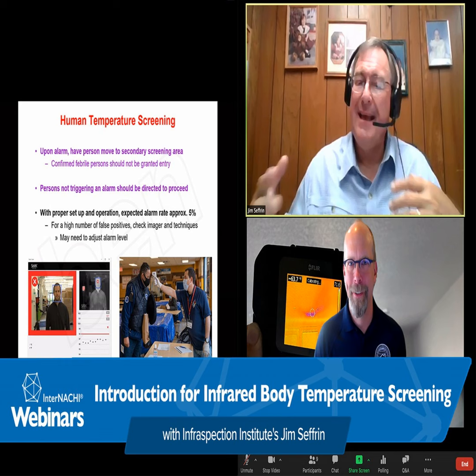I want to talk just a little bit about the need for secondary verification. Infrared is not a standalone tool when it comes to elevated body temperature screening. As part of a human body temperature screening system, we're going to have not only our imaging radiometer, or if you prefer, our infrared camera, but we also must have a clinical grade thermometer as part of that screening system. The infrared radiometer or imaging radiometer or infrared camera is a screening tool. It generates pass-fail results. So it is pass-fail testing that identifies potentially febrile persons. Be aware that infrared imaging equipment is subject to measurement errors due to differences in screened persons, operator error, or within the imaging system itself.